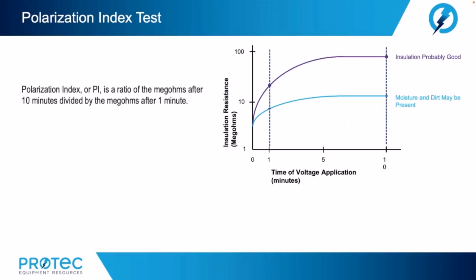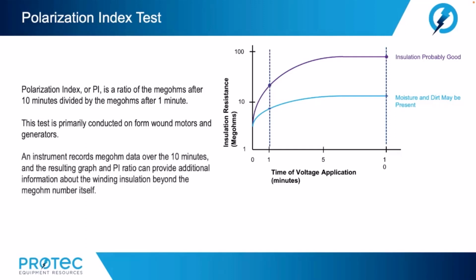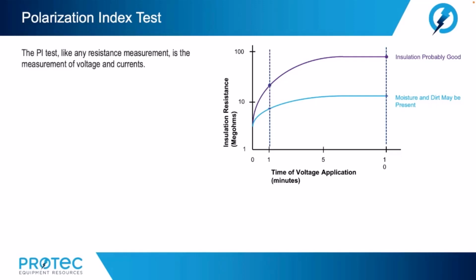Polarization index, or PI, is a ratio of the megohms after 10 minutes divided by the megohms after 1 minute. This test is primarily conducted on form-wound motors and generators. An instrument records megohm data after the 10 minutes, and the resulting graph and PI ratio can provide additional information about the winding insulation beyond the megohm number itself. The PI test, like any resistance measurement, is the measurement of voltage and currents. PI is the ratio of leakage currents assuming constant voltage.